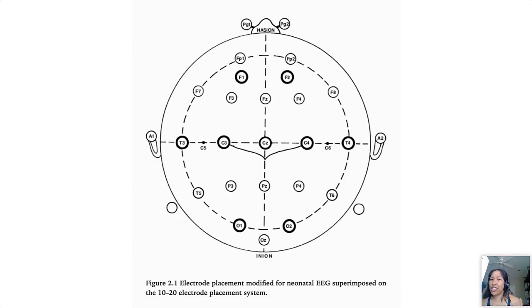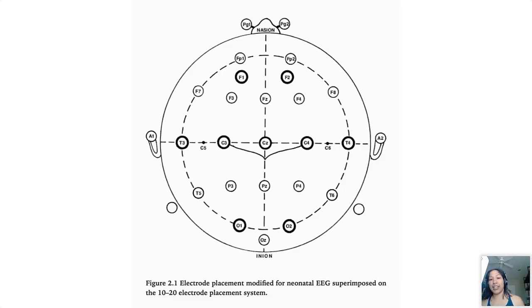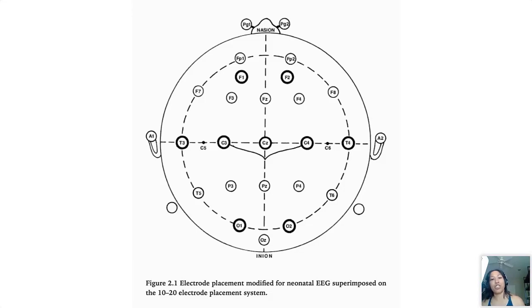In the gray in the background you can see the traditional 10-20 montage that we would use in an adult. Essentially if you were to try to do the adult montage on a very small neonate's head, the fields would just be completely overlapping and it wouldn't be very readable, especially in our preemies. So we use a special neonatal montage.